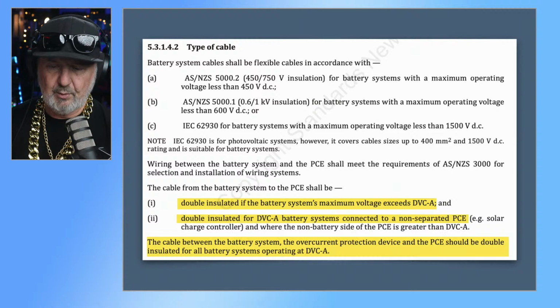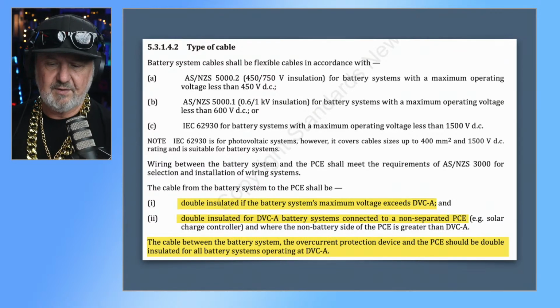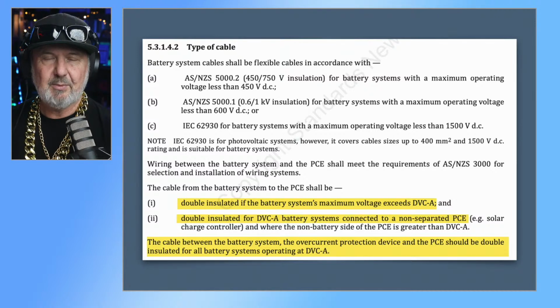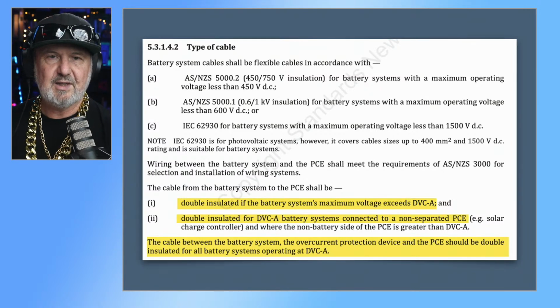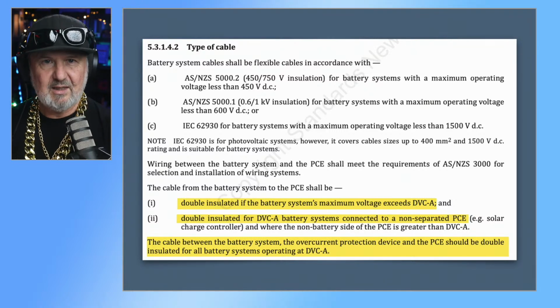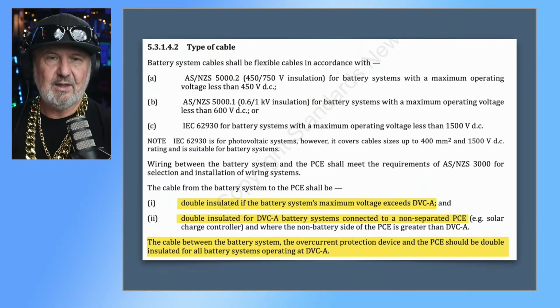And we've got a question here. Arthur says, what if the PCE manufacturer forbids disconnecting the minus between the inverters? Okay, so manufacturers' recommendations must be followed if they're additional to the requirements of our safety standards, but they cannot take away the requirements of our safety standards. So in Australia and New Zealand, under all our standards for battery systems, we always require double pole isolation.